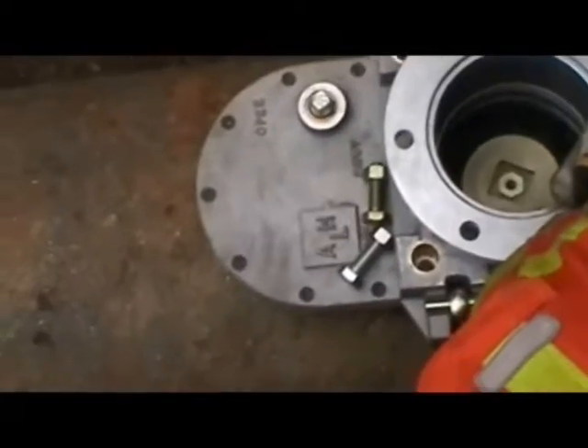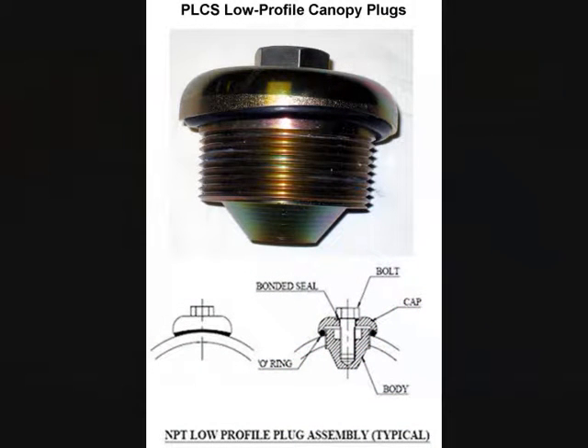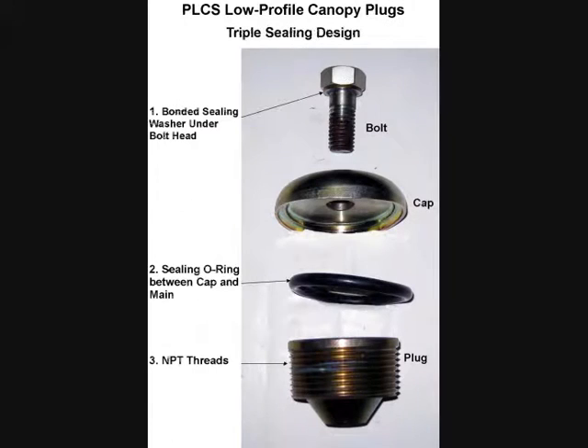These plugs offer superior sealing capability as opposed to the standard malleable plug. The NPT threads are precision-manufactured, offering high-quality threads. This is important since today many plugs are made in other parts of the world with unpredictable quality standards. If any gas happens to get past the threads, the plug's contoured cap compresses the sealing o-ring against the main when the bolt is tightened to further ensure a gas-tight seal. The bonded sealing washer under the bolt head completes the seal.